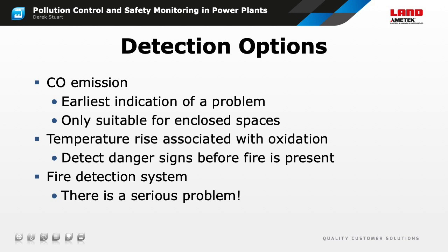Temperature sensors are another option for monitoring and preventing spontaneous combustion. They give a direct indication that heating is occurring. Because of the time taken for a measurable temperature change to build up, a temperature sensor gives a slower indication of a problem compared to a CO monitor. However, it can be used in an open area such as a coal pile or a conveyor belt which is exposed to air movements. Finally, there's a fire detection system. By the time this triggers, we have a serious problem and are definitely beyond the stage of taking preventative action.